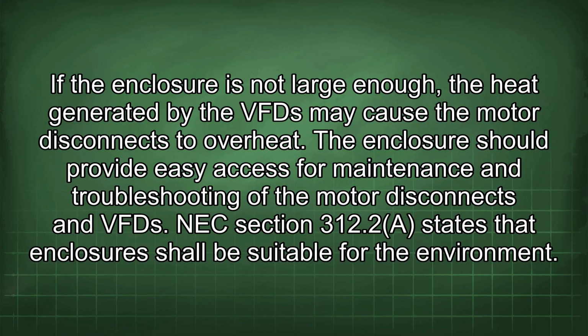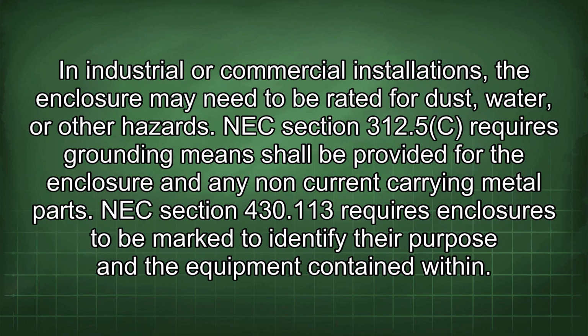NEC Section 312.2 states that enclosures shall be suitable for the environment. In industrial or commercial installations, the enclosure may need to be rated for dust, water, or other hazards. NEC Section 312.5(C) requires grounding means shall be provided for the enclosure and any non-current carrying metal parts. NEC Section 430.113 requires enclosures to be marked to identify their purpose and the equipment contained within.